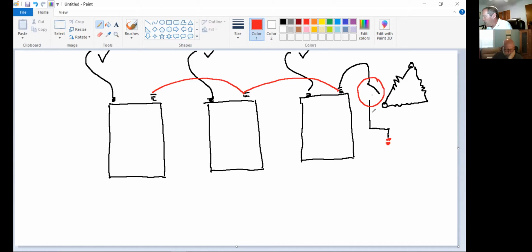Let's say I'm in the de-energized state. I close switch 1, open switch 2, open switch 3, and open switch 4 - I've added the 4th in there. That prevents it: as soon as I close switch 1 and take my path to ground, it's not floating anymore. All imbalanced load goes to ground, not to the other two transformers.